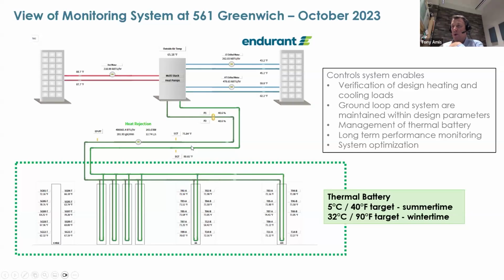And what we're looking at is this temperature here, the outside air temperature, and then what we can do is a simple coefficient of performance check to then determine, well, should we be running the ground source heat pumps or the air source heat pump? What's the most energy efficient way of heating and cooling? That's one of our parameters. But the other parameter is that as we're running into a winter season, what we're wanting to do is to try and warm this ground up under the building to around 90 degrees Fahrenheit by providing as much cooling to the building as possible.